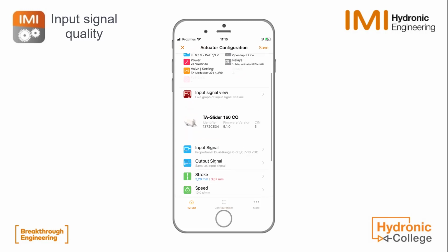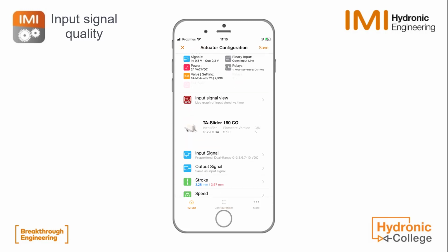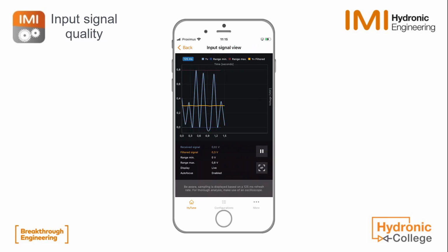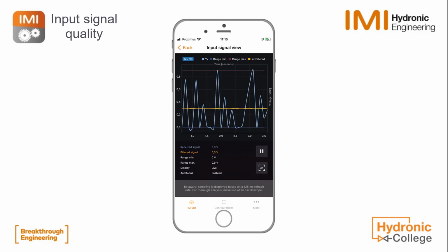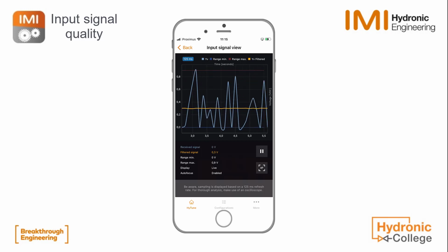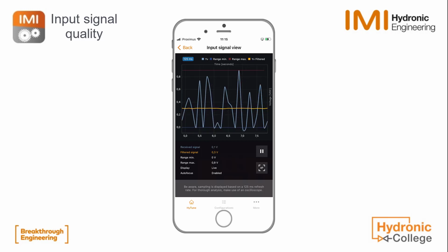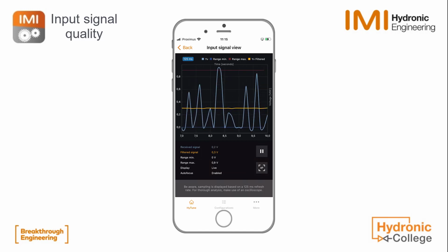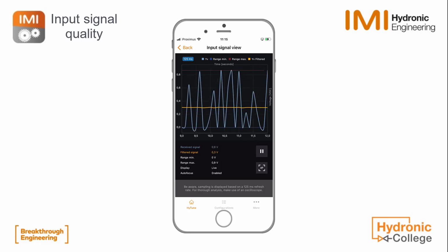Now, what could be behind these fluctuations? It is incorrect wiring, long cables sometimes, and sometimes high frequency electrical devices in the same plant are disturbing the input signal on the input signal line.